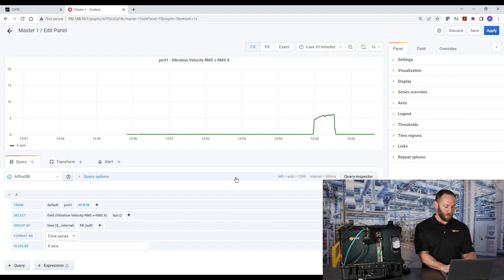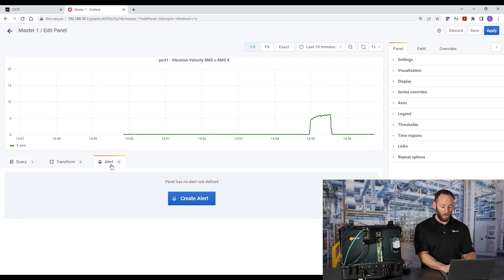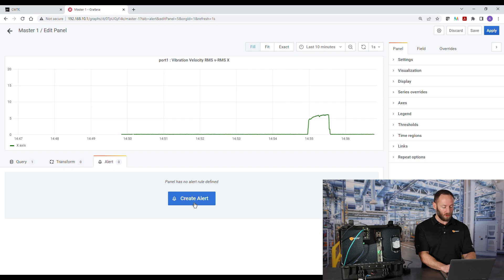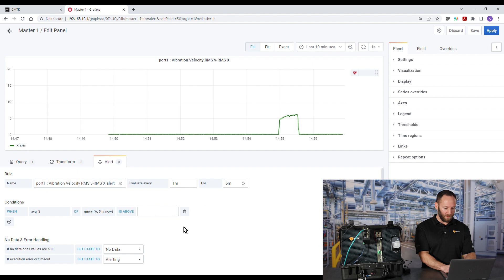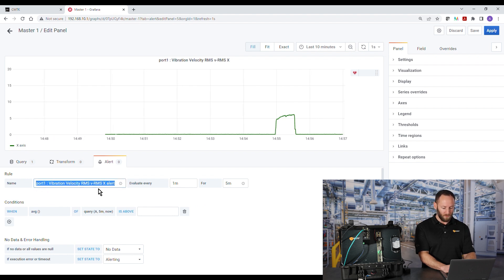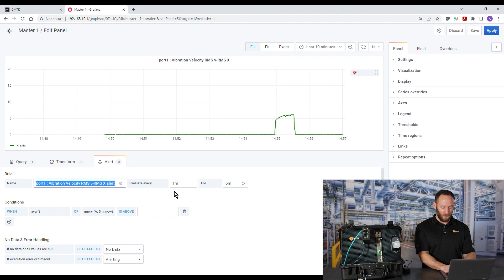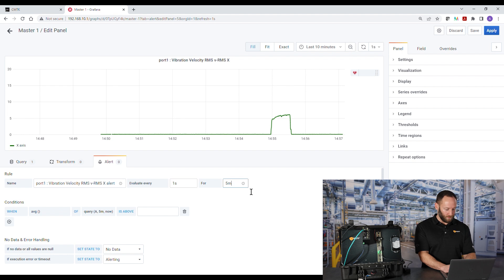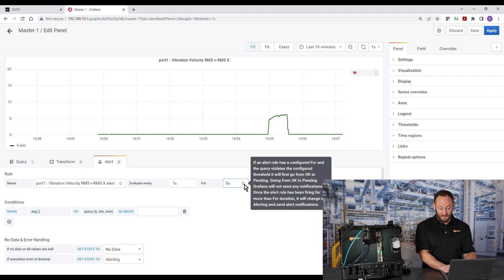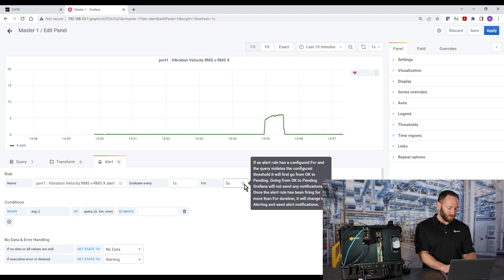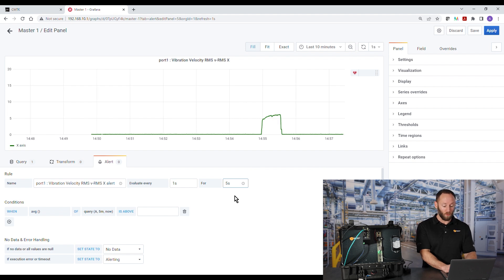Next, I'll go to alerts and we get to set up alarming. We'll specify when we want to get an alarm. On the alert tab, we'll click create alert. So I'm going to select a variable. And here I want the vibration velocity RMS value. So I'm going to evaluate. Instead of every minute, we're going to change to one second for this video. Just so we can see it updated faster. And the condition has to last for at least five seconds prior to sending an alarm. The reason being here is that noise or spikes may cause unnecessary alerts.